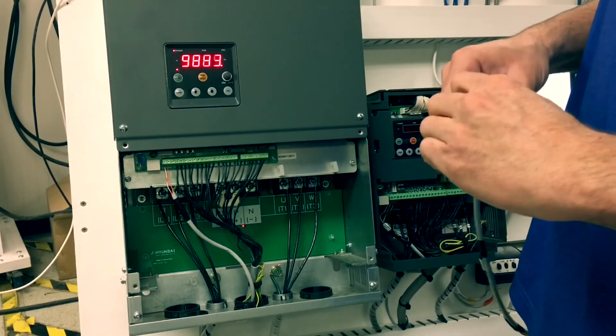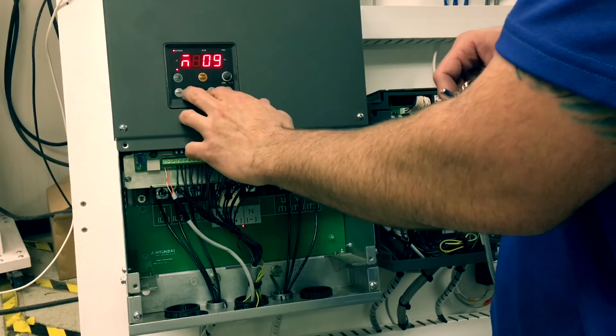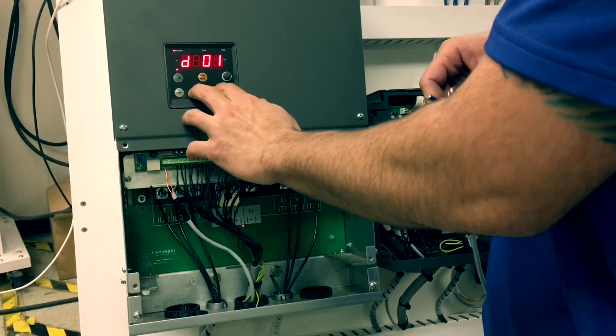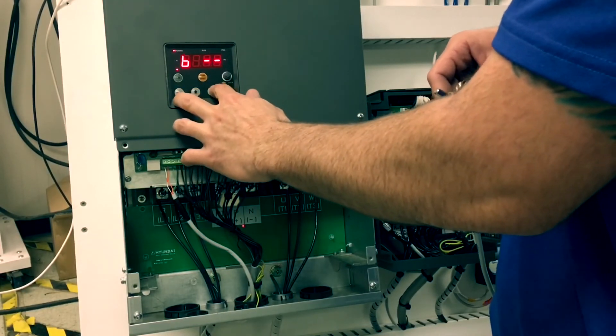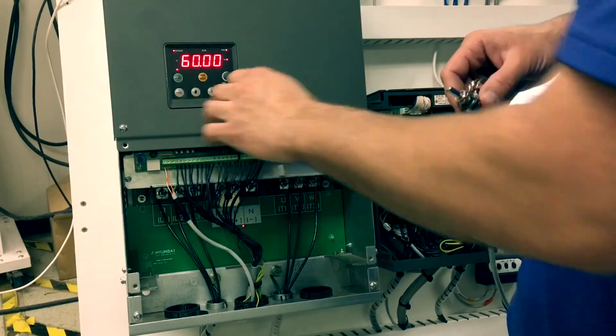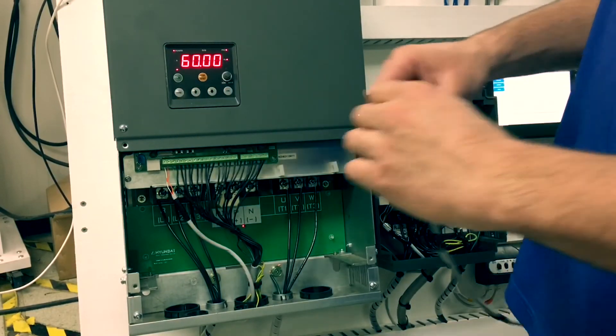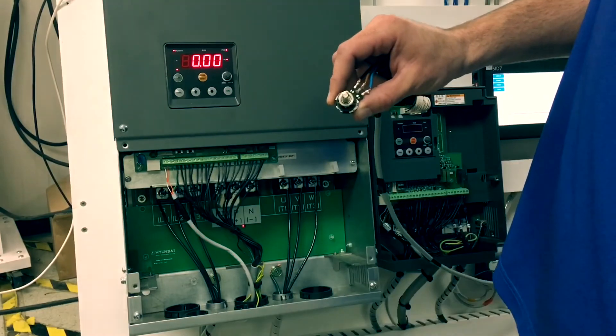Now our speed potentiometer is fully calibrated. We can verify this by going to d01 parameters to show our speed reference in hertz. We show 60 hertz all the way up and 0 hertz all the way down.